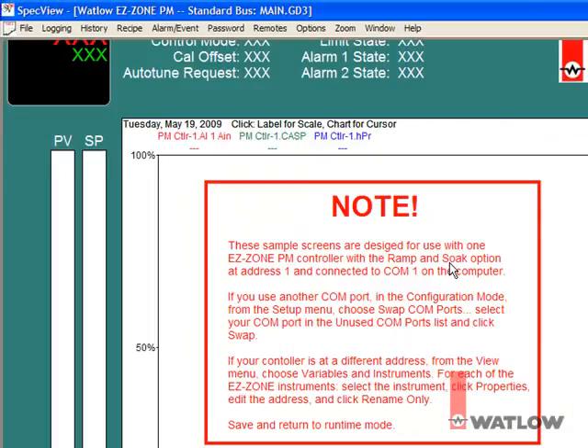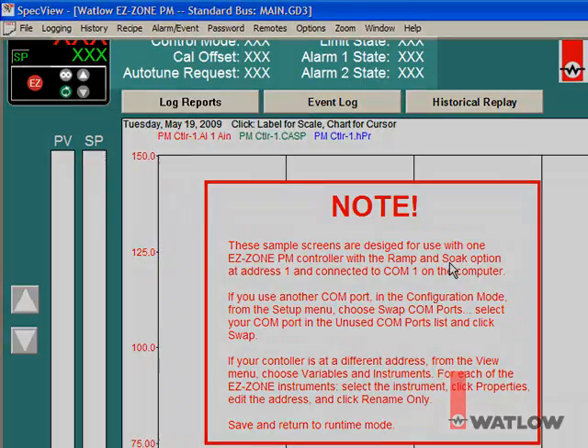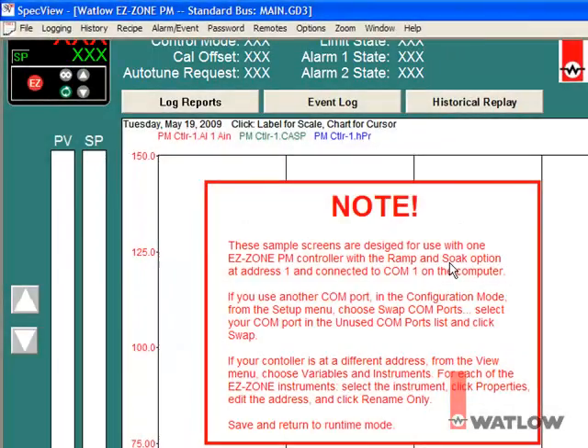SpecView opens the PM sample configuration and enters the runtime mode. If your controller is not connected to COM1 and set to address 1, SpecView will not be able to communicate with the PM, and three X's are displayed instead of current data. So we will need to edit the SpecView configuration to match the communications setup.